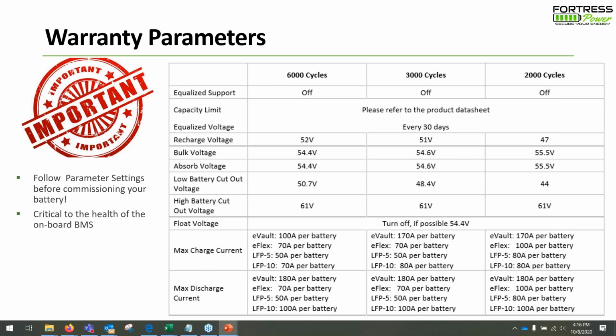So here is the list of warranty parameters from the website. From the warranty, in general, we're going to go with the left. If we're going to make these LFP10s and Schneider 6848 systems work, we have to make sure that they're very gentle on the battery. The low battery cutoff voltage should be around 50 or 51, something like that, 50.7. The bulk and absorb should be low, 54.4, around there. Recharge voltage, 52. No equalization. The max charge current should be low. I would say 70 amps per battery. Max discharge current, I would say lower, probably 80 amps per battery, just to make sure that there are no spikes and no problems with the BMS. Okay.